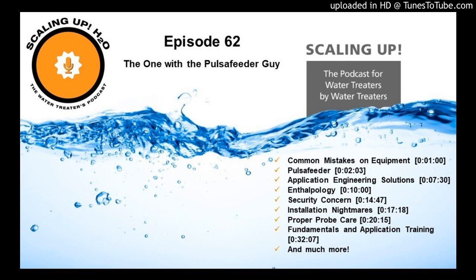We have many clients online, and it allows us to do our job better, especially with Legionella testing. As soon as we get a positive back from the lab, we can make the adjustment right then and there. If we didn't have that, we'd have to stop what we were doing and go all the way out to make that adjustment. Now we can make the adjustment as soon as we get the notice, and then start driving to that account to do whatever else we need, running other tests and checks because our product has already fed.